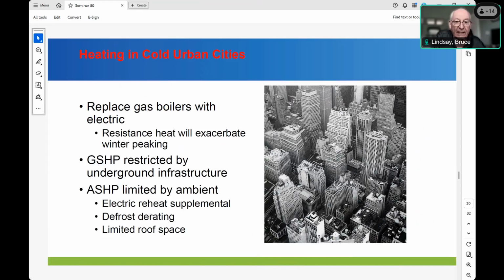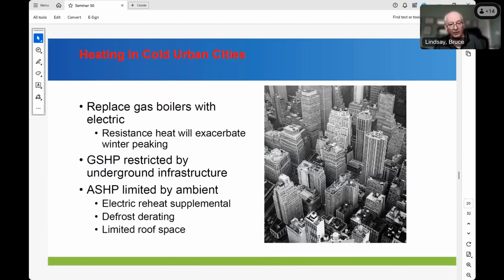We want to get rid of gas boilers in cold urban cities. Obviously, New York's the key market right now. And so it's really easy. Just rip out the gas boilers and put an electric boiler in. If you do that, you're going to have a world of hurt. Couple things. One, you may not have sufficient electric capacity for heating the building electrically. Two, if all of your neighbors decide to do that, you may have to put in a new utility substation, which is incredibly expensive and a long lead time. And obviously, everyone putting electric heat is going to exacerbate your winter peak demand.